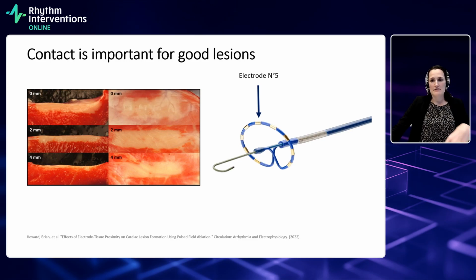Similarly, traditional surrogates of effective lesion delivery, like first pass isolation or time to isolation, cannot be used as a criteria for effective energy delivery with PFA. Consequently, it's important that optimal apposition between the catheter and the tissue is achieved prior to delivering the PF energy. Due to its forward tilt, the array might act like a spring and often provides the operator a tactile feedback when he's in contact with tissue.